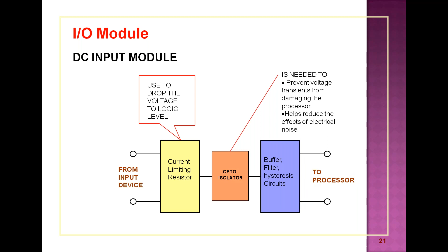DC input module: we have an opto isolator. The first step is to drop the voltage to logic level. Then the opto isolator prevents voltage transients from damaging the processor and helps reduce the effects of electrical noise, since we don't want that noise reaching the CPU. Then we have buffer, filter, and hysteresis circuits, all before it gets to the processor.